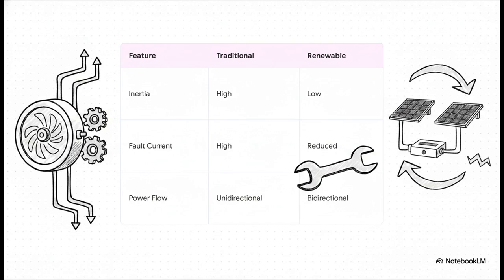They have super low inertia, drastically reduced fault currents, and they create a bidirectional flow of power. This throws a massive wrench into traditional protection coordination. If that fault current is too low, those relays and circuit breakers might not trip fast enough, or honestly, they might not trip at all.